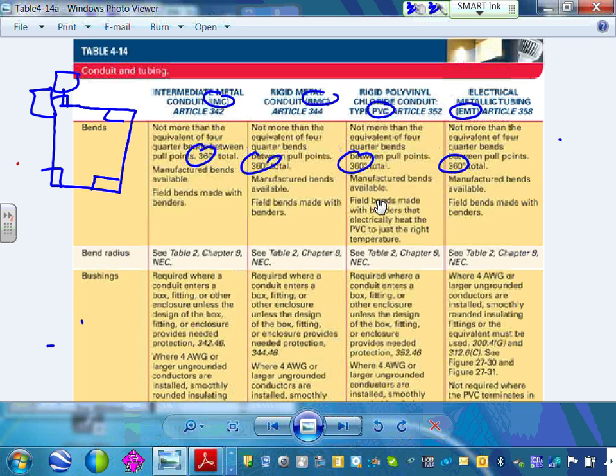You put a box. So gentlemen, what do you do? You put a box here and you start over. Anybody know why? Remember, you're pulling wires out of these suckers. How do you pull a wire through 4 90s? The electrician who's going to be pulling it, if you design something like even 4 90s, they will be cursing you, especially if you're putting 500 KCM, 4 of them. Talk about cursing. So typically that's the max, guys, you wouldn't even go there.